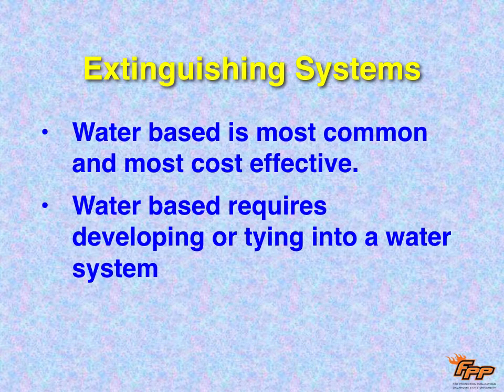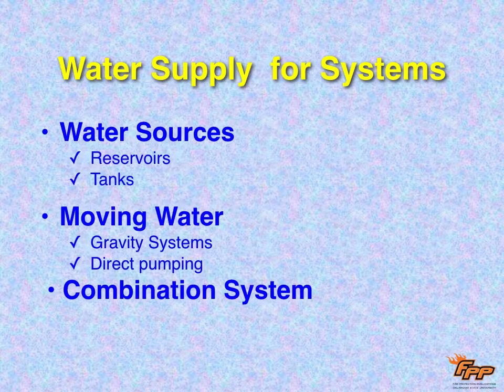Okay, extinguishing systems. We're halfway done, believe it or not. There's a lot to talk about with extinguishing systems. Water-based is the most common, and it does require developing or tying into a water system. So for tying into a water supply system, we need to understand the system, that there's water sources. We're going to have, like here in California, aqueducts and reservoirs and systems with tanks. We want to move that water throughout the community, and any building that has fire sprinklers or any kind of water-based system, we need to get that water to their property. They're going to have to tie into it.